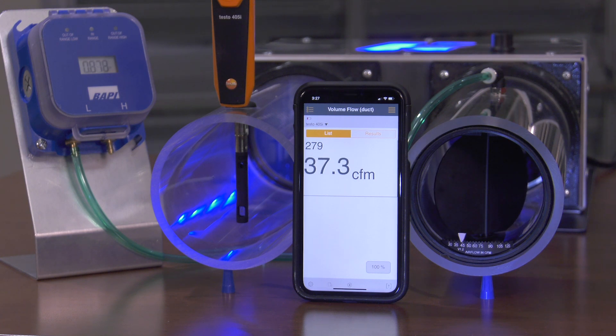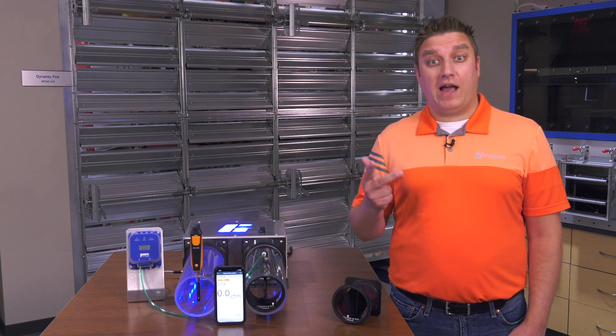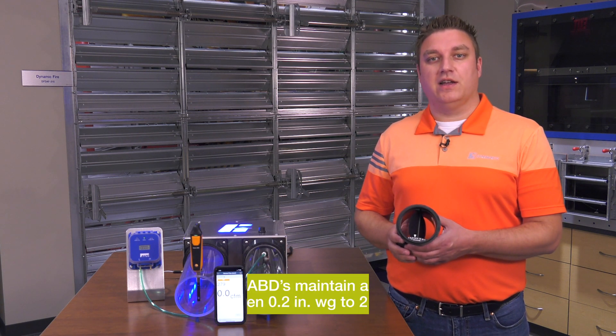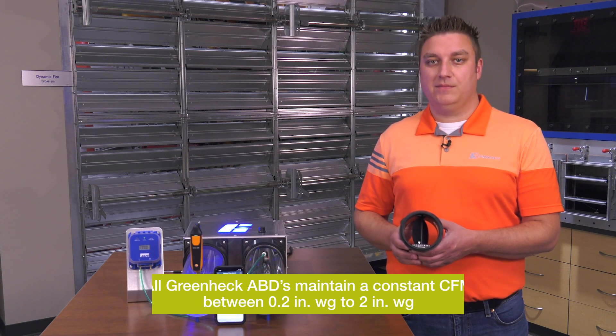Unlike competitive valves, which require different models for low pressure, standard pressure, or high pressure applications, all of Greenheck's ABDs maintain a constant CFM anywhere between 0.2 inches water gauge all the way up to 2 inches water gauge.